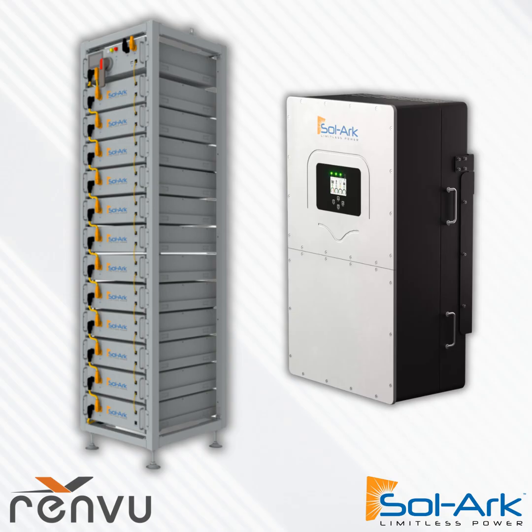In residential, the idea of an essential loads panel without whole home backup—we've run away from that concept. Homeowners want whole home backup, not essential load backup. But Sol-Ark has always listed our products so you can plug in anywhere on a main service panel and provide backup power only to an essential load panel, regardless of the interconnection size, independent of the 120% interconnect rule.